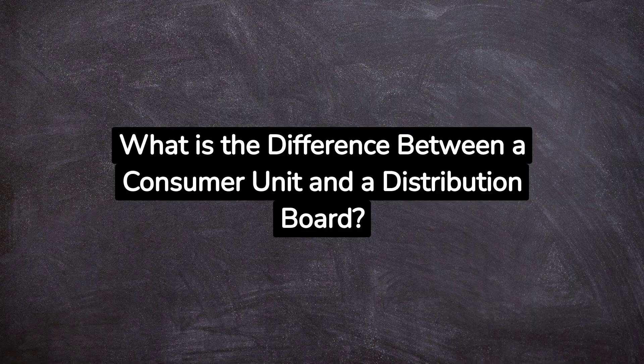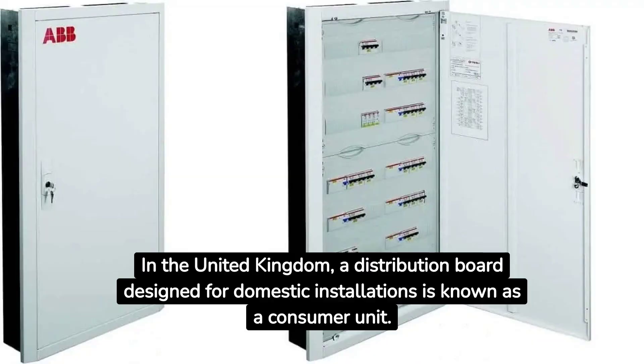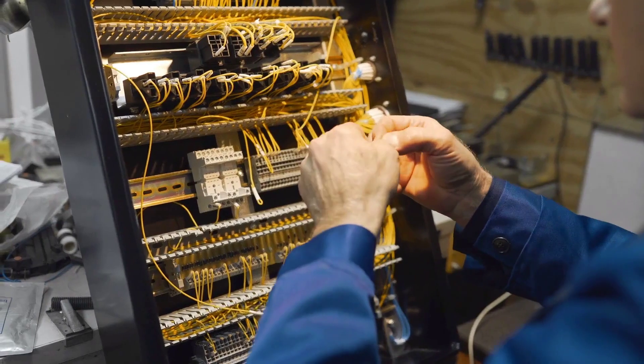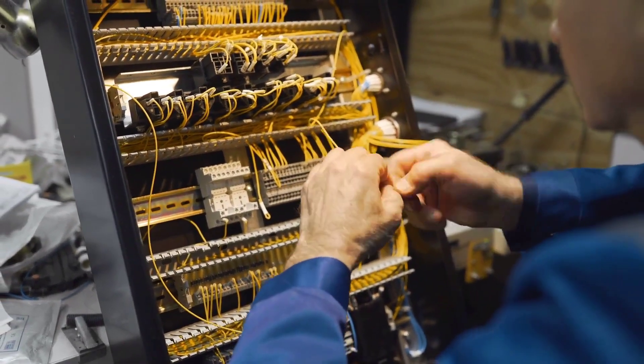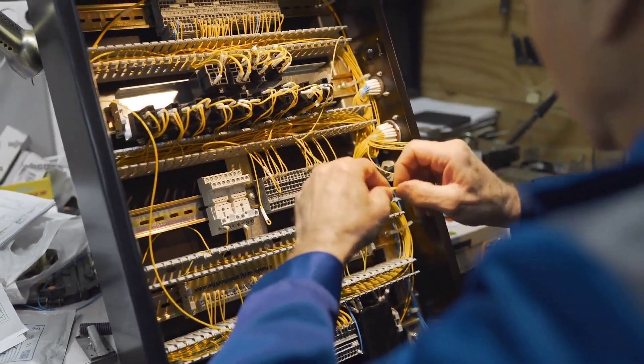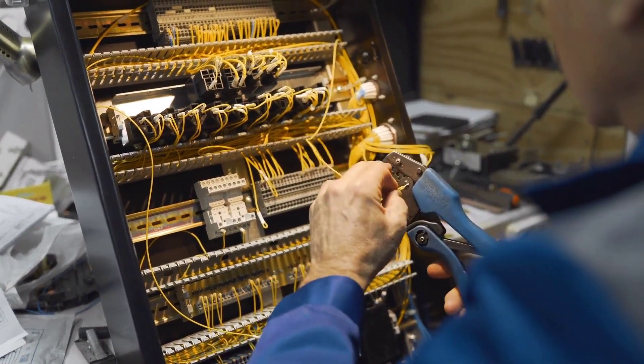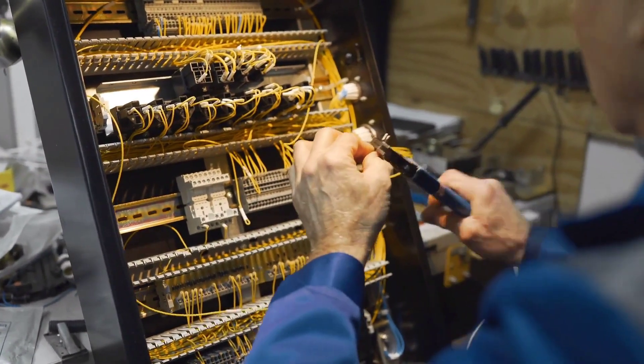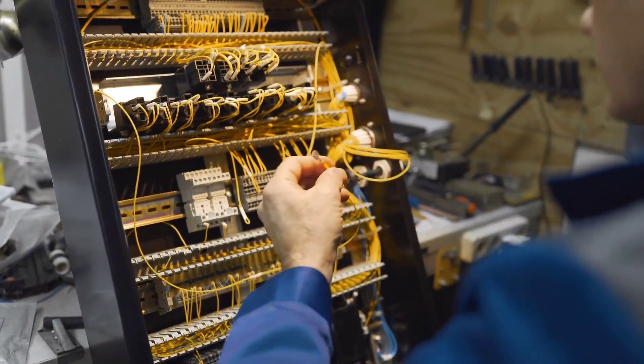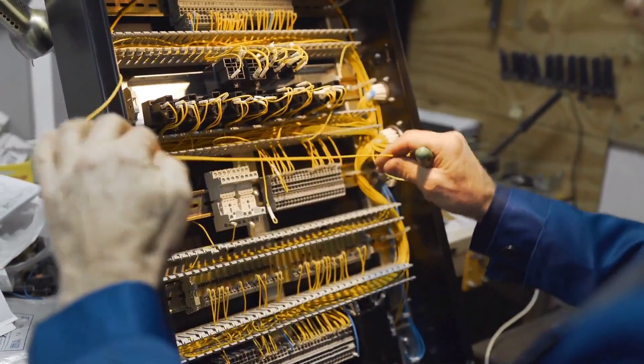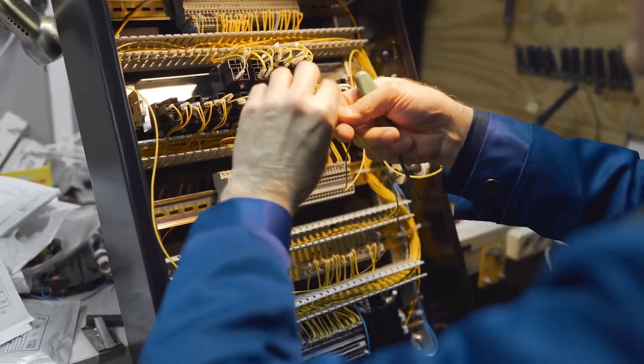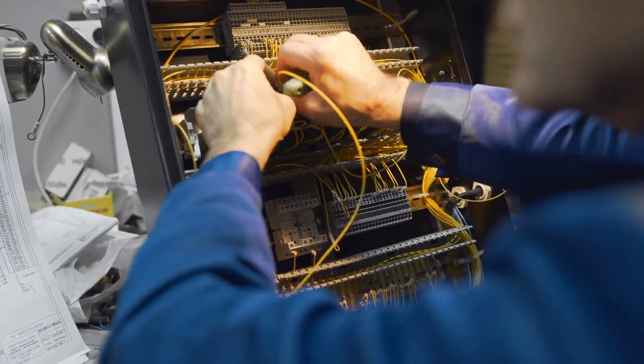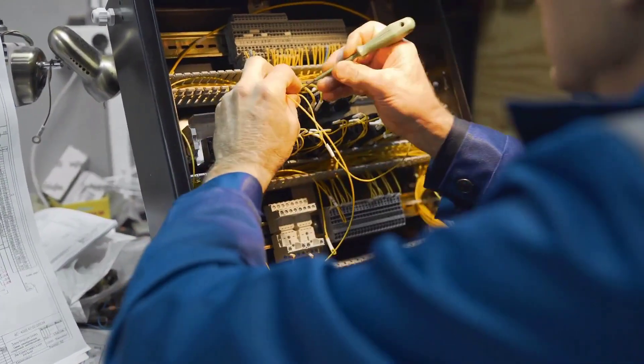What is the difference between a consumer unit and a distribution board? In the United Kingdom, a distribution board designed for domestic installations is known as a consumer unit. A consumer unit may also be known as a consumer control unit — a particular type of distribution board comprising a type-tested coordinated assembly for the control and distribution of electrical energy, principally in domestic premises, incorporating manual means of double-pole isolation on the incoming circuits and an assembly of one or more fuses, circuit breakers, residual current-operated devices, or signaling and other devices proven during the type test of the assembly as suitable for such use.